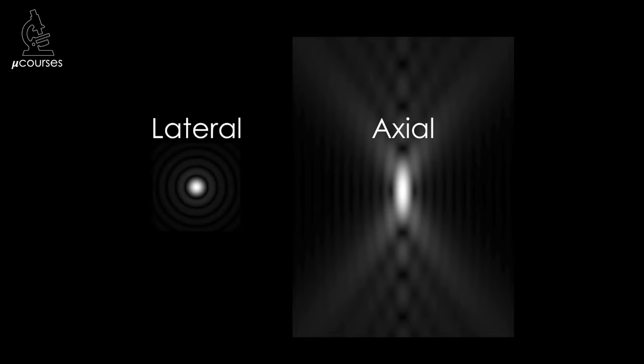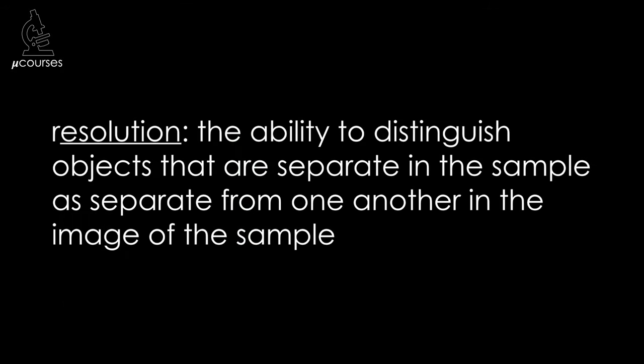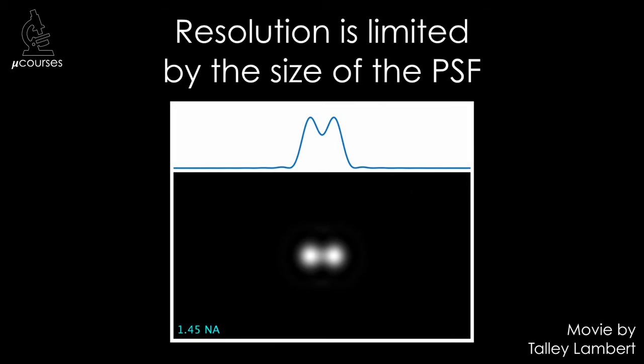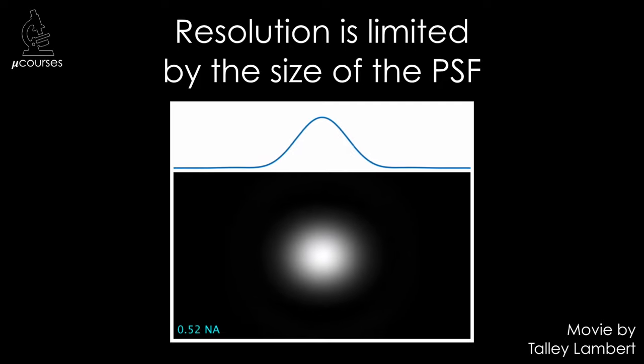When we talk about the size of the point spread function, we're generally referring to the size of the maxima. An image of a small point source of light is going to appear as a point spread function in the image. Small points in your sample are therefore going to have this Gaussian shape of the point spread function maxima. And remember that resolution is defined as the ability to distinguish objects that are separate in the sample as separate in the image. So as the point spread function gets bigger, the Gaussians blur together, and we lose the ability to resolve objects.